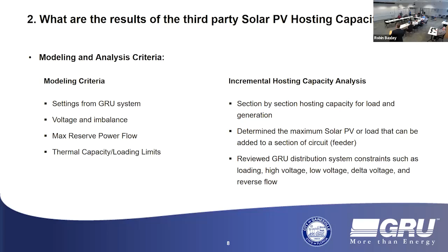Okay, here we are looking at results of the study, and we are showing 2 substations here. The first one is Kelly West. Kelly West has two substation transformers in it, T30 and T39. They are different sizes. One is sized at 33.6 MVA. The other is sized at 56 MVA. And you can see we're showing 7 circuits here, and the maximum allowable PV generation varies for each circuit. The minimum amount out of this particular substation is 0.83 megawatts, which would be allowed to be connected to circuit 285, whereas a maximum of 3.19 megawatts would be allowed to be connected to circuit 282.